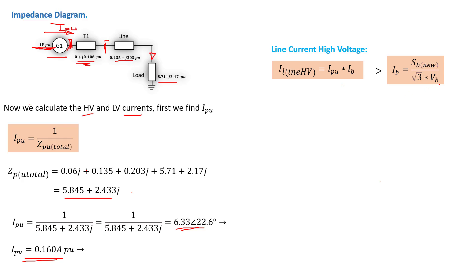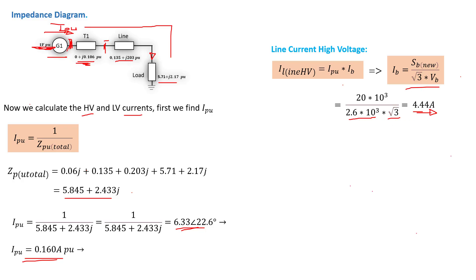I_base equals S_B new divided by the square root of three times V_B, where V_B is the voltage of the generator. Replacing values: S_B is 20 × 10³ VA, V_B is 2.6 kV with the square root of three. That gives us I_base. The line current from the generator is then 0.16 times 4.44, which gives us a current of 0.71 amp.